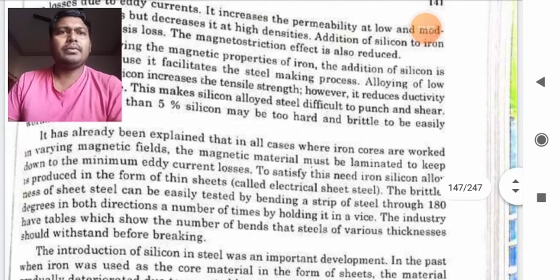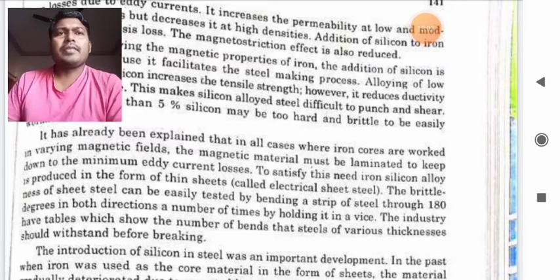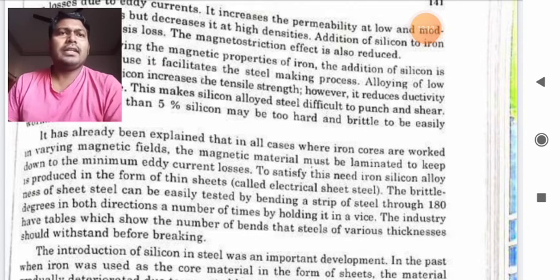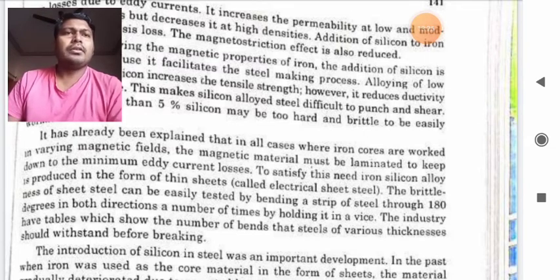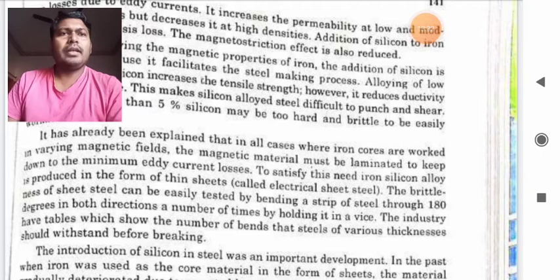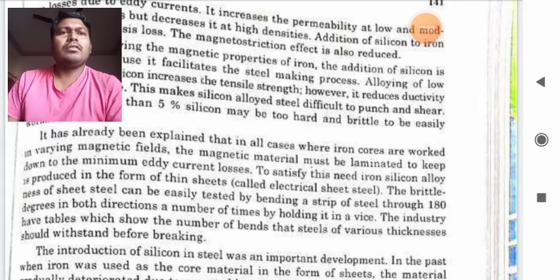It has been explained that in all the cases where iron cores are worked in varying magnetic fields, the magnetic material must be laminated to keep down to the minimum eddy current losses. To satisfy these needs, iron-silicon alloy is produced in the form of thin sheets. The brittleness of steel can be easily tested by bending a strip of steel through 180 degrees in both directions, a number of times by holding in a vice. The industries have tables which show number of bends that steels of various thickness should withstand before breaking.